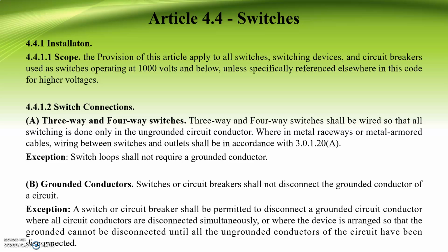So B, grounded conductors. Switches or circuit breakers shall not disconnect the grounded conductor of a circuit. So exception, a switch or circuit breaker shall be permitted to disconnect a grounded circuit conductor where all circuit conductors are disconnected simultaneously, or where the device is arranged so that the grounded conductor cannot be disconnected until all the ungrounded conductors of the circuit have been disconnected.